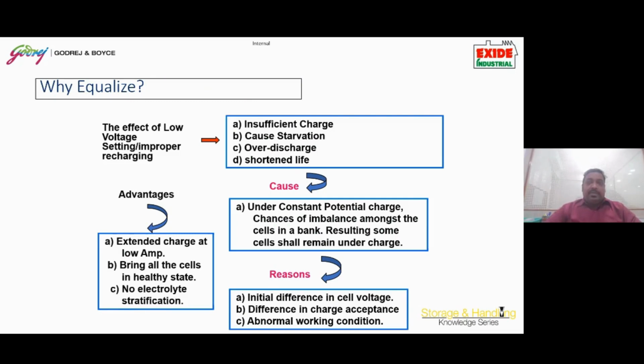Equalizing charge need not be done every day; it can be done on a weekend or a weekly off day, so that only 3, 4, or 5% of the current goes in. This current will try to balance the cells. Since all the cells are in series, the current will flow into cells that are starved, deprived, or at a lower potential, and try to charge them.